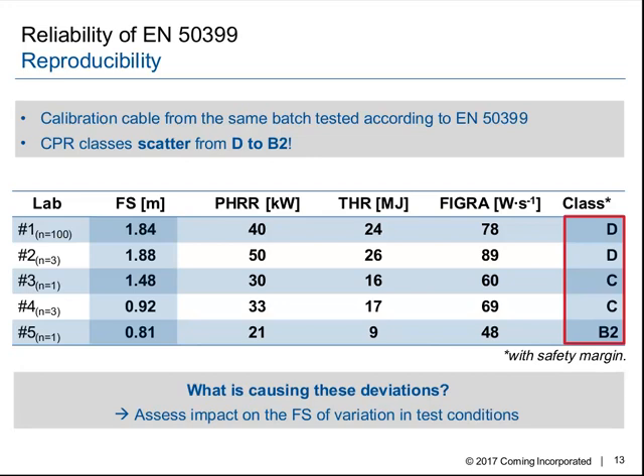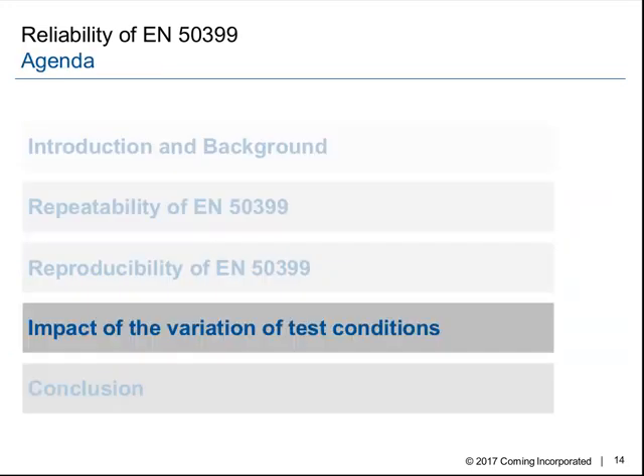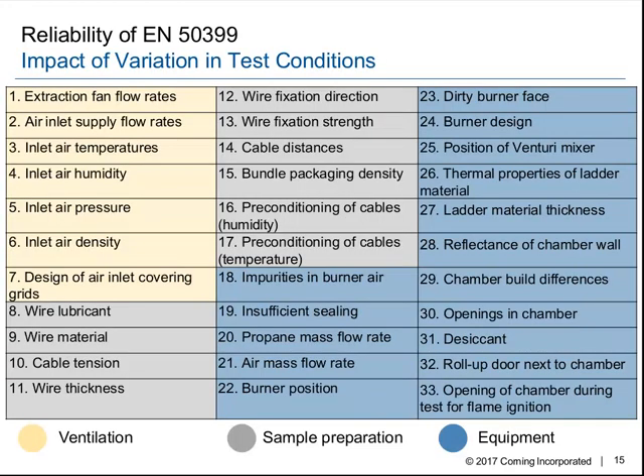So the strong question came up for us: what is causing those deviations? We did a big test plan in order to assess the impact of different variations of test conditions on the flame spread. And this is exactly what I would like to show you now. So we did a big test plan with our calibration cable. The first thing was that we studied the standard in order to identify parameters which are not stringently defined, or not defined at all, or defined in ranges.